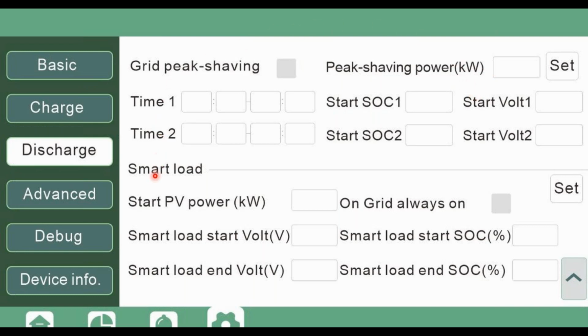Here, smart load, when enabled, allows the generator port to actually become an output. So by enabling smart load functionality, you can hook up a load. It's basically like smart load management, but instead of six or eight, it's one, right? But it has that capability. It will enable itself when two conditions are met: when the battery is at a certain state of charge that we stipulate here, and the PV power surpasses the power stipulated here as well. Otherwise, you can set it to on grid always, and the load will be provided by the grid.